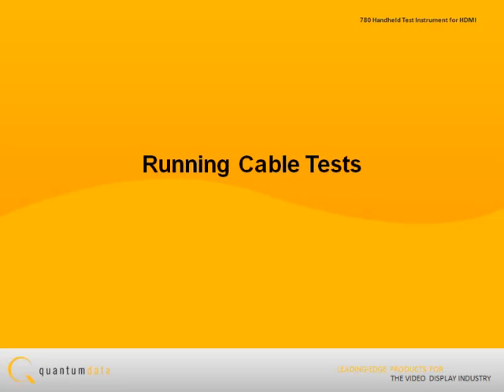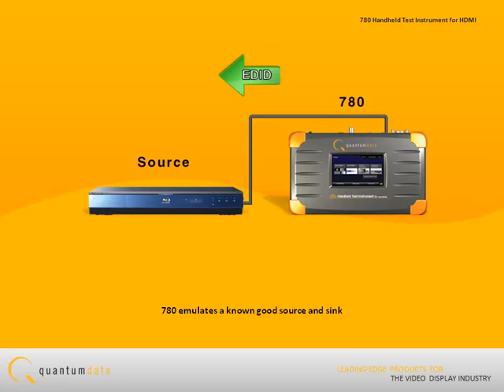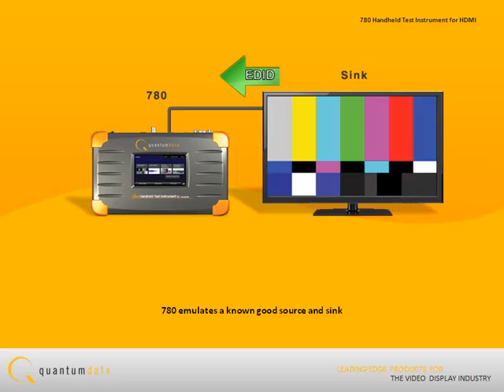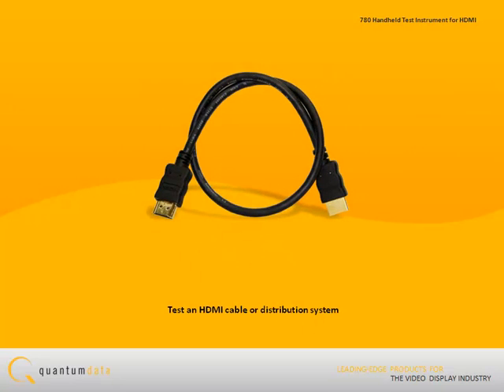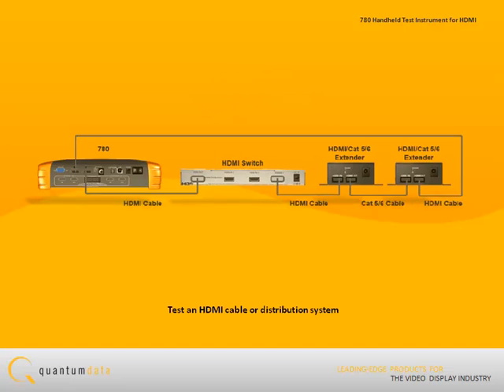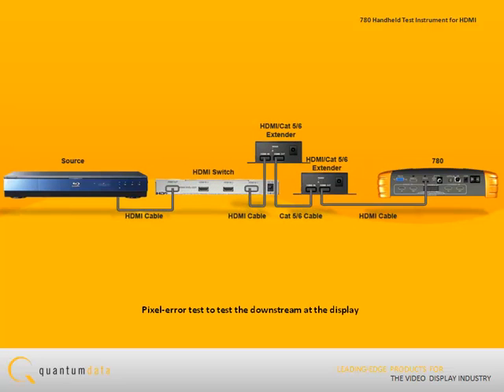Running cable tests on an HDMI cable. The 780 test instrument emulates both a known good HDMI source device and a known good HDMI sink device. Therefore, it can test an HDMI cable or distribution system as long as the two ends are collocated. If the cable or distribution system is already installed, the 780 has a related feature called the Pixel Error Test that enables you to test at the far end at the display.